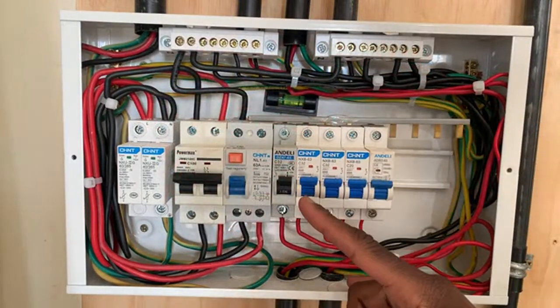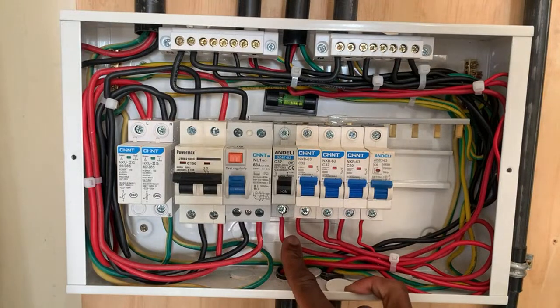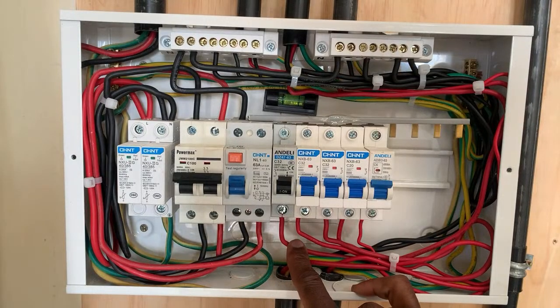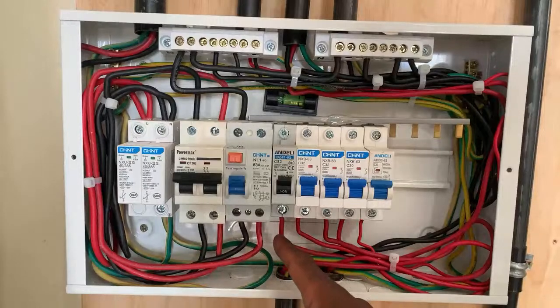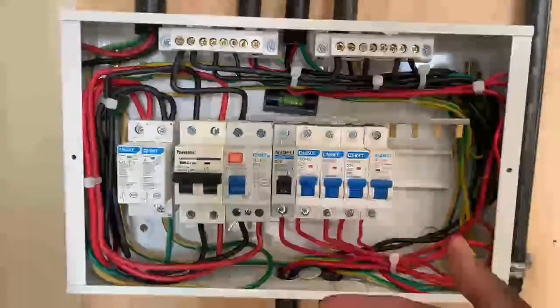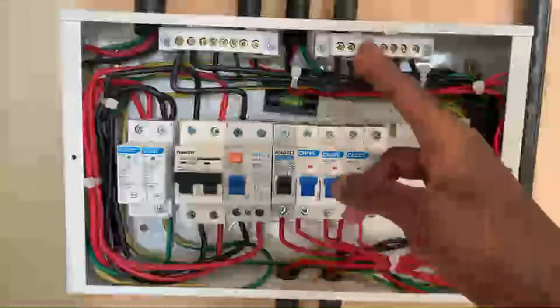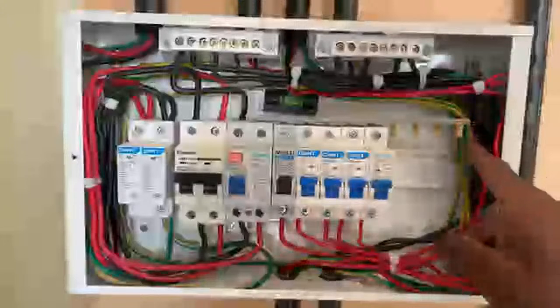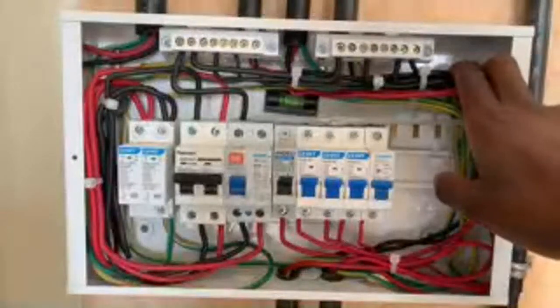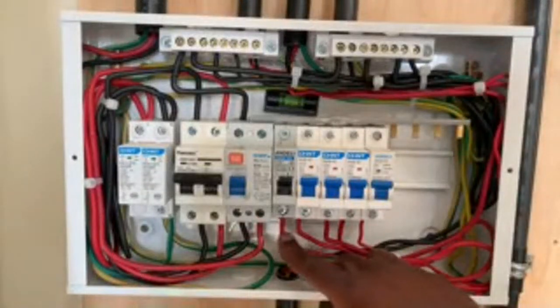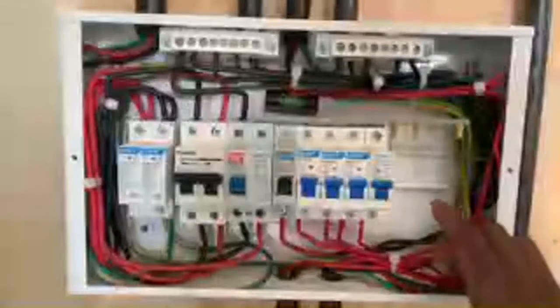Why? For every circuit that you connect, let's say a 4.0 millimeter square wire, this is probably that heating circuit we have been talking about. Let's say it is an electric cooker circuit, or an instant shower head circuit where you're using that 4.0 millimeter square wire for the phase, which is the red for our case here in Kenya, and you have the return connection. The same must apply when it comes to the earth connection. When you're connecting to the earth bars for that specific circuit, you must have a 4.0 millimeter square. Why? From this MCB here, we have said that power will go all the way to the electric cooker. Then it has to form a complete circuit and come back.